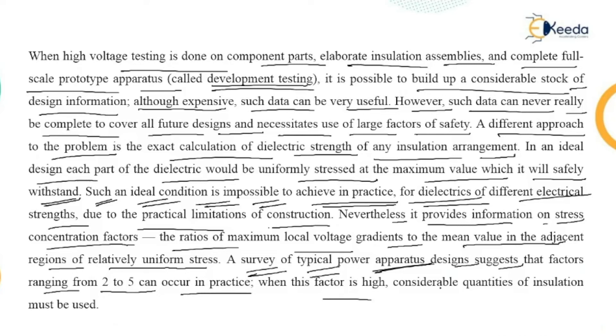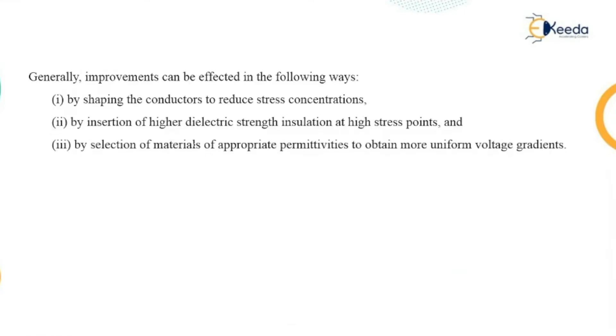When this factor is high, considerable quantities of insulation must be used. Improvements can be made in the following ways: by shaping conductors to reduce stress concentrations, by inserting higher dielectric strength insulation at high stress points, and by selecting materials of appropriate permittivities to obtain more uniform voltage gradients. That concludes this understanding of surge voltage, their distribution and control.